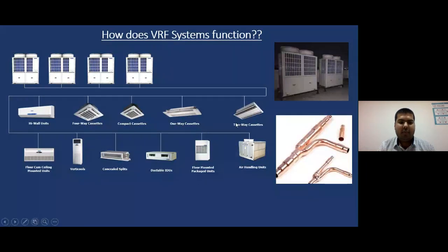Suppose the person sitting in a ductable IDU room requires a temperature of 24 degrees Celsius, it can be done at the same time when a person sitting in a two-way cassette room requires 28 degrees Celsius. So that flexibility VRF gives to the occupant. These are some photographs of a VRF outdoor unit, what it looks like when we install it at the terrace of a building. And when we connect all the machines, you can see these branches. These branches are joined through copper joints which are called ref nets. This is a particular photo of a ref net, a copper joint. The pipe will go straight, and there is a branch, and it would be connected to a ductable IDU or a concealed split or any indoor unit you say.